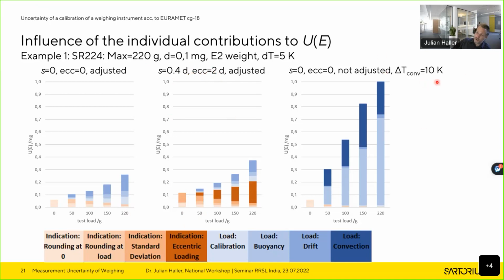But if you use not acclimatized weights, so you have a temperature difference between the weights and the environment of 10 Kelvin, you see that these contributions absolutely dominate the complete uncertainty. So it really depends on the particular situation, particular case, and also on the particular weighing instrument that you're calibrating.